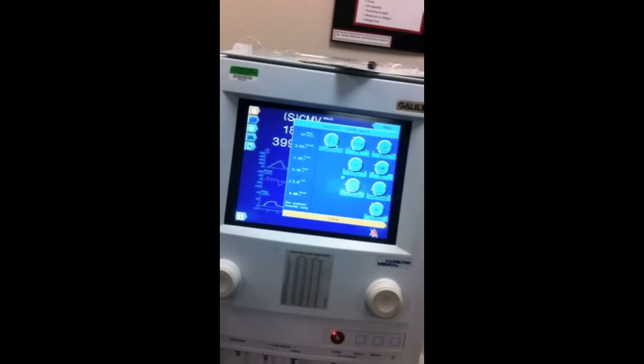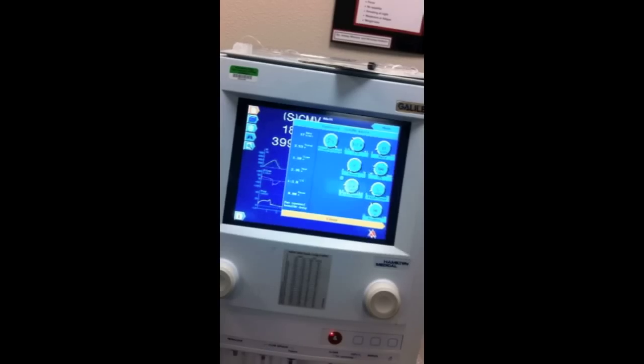You'll notice in this ventilator, in assist control, we do not have an apnea backup. Because the logic is we're in assist control, we don't need an apnea backup, which technically you don't. The ventilator is going to breathe for the patient. You'll see if you go to SIMV, though, there is an apnea backup there. So that's why you're going to see it, and sometimes you won't.